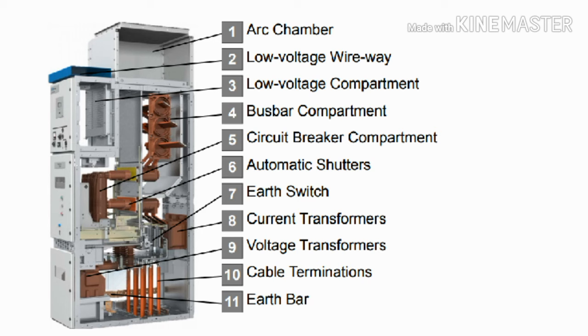The voltage transformer steps down the voltage to 110 volts, and that 110 volts helps to control the control supply of the switchgear panel. Tenth is the terminal cable termination — these are the outgoing connections of the switchgear panel that connect to the load.